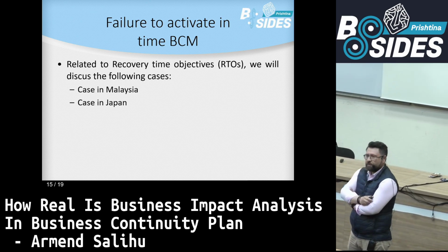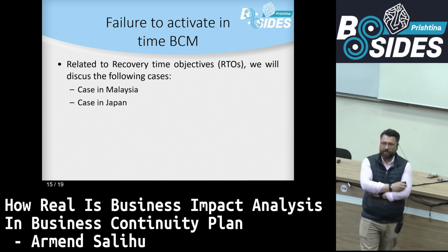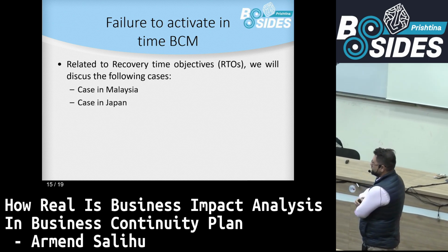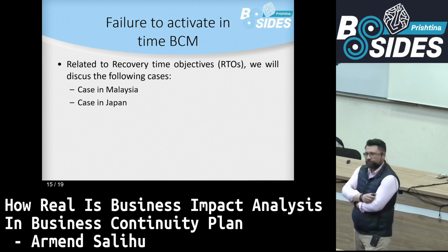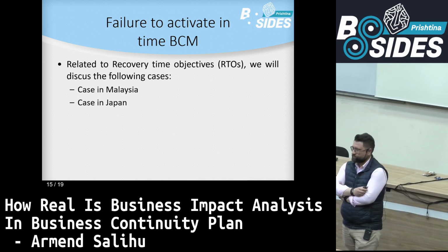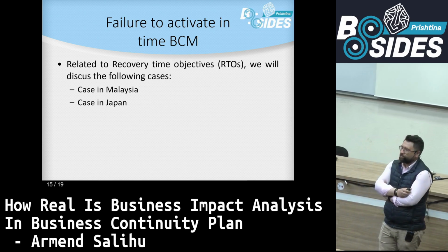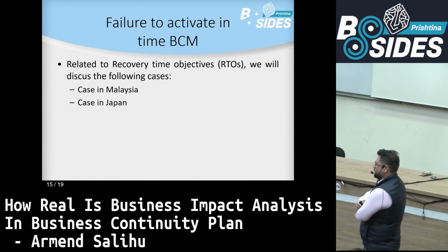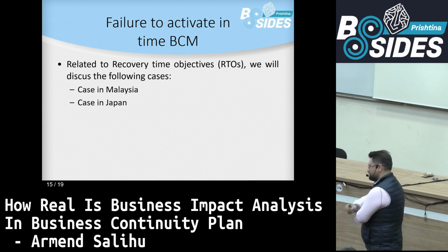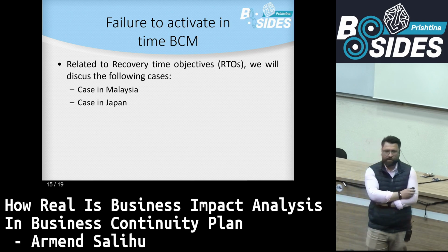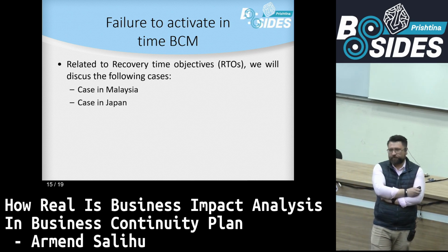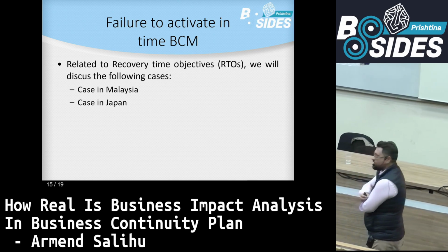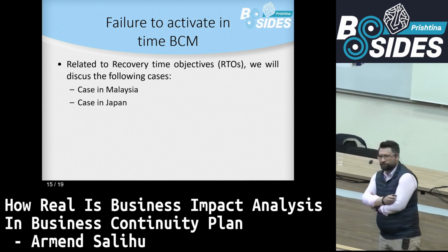Another case that we encountered during our interview was in Japan. A bank in Japan located its main data center on the -1 floor. Honestly speaking, it was the board's decision to put the main data center on the -1 floor. And even worse, the electricity supply was on that floor. So they had water flooding, and a key IT staff member was locked inside. He couldn't escape from that place.